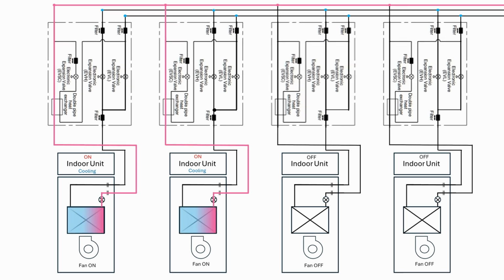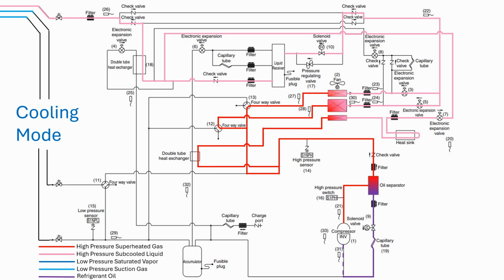As the metered refrigerant passes through the indoor heat exchanger, it absorbs heat from the space. The superheated low-pressure gas then travels back to the branch selector, where it is split and sent back to the outdoor unit on the suction line and the high-pressure line. As the refrigerant approaches the outdoor unit, please notice that the 4-way valve on the high-pressure line is positioned to route the refrigerant to be joined with the suction gas just ahead of the accumulator. The low-pressure gas then leaves the accumulator and travels back to the compressor to start this process over again.